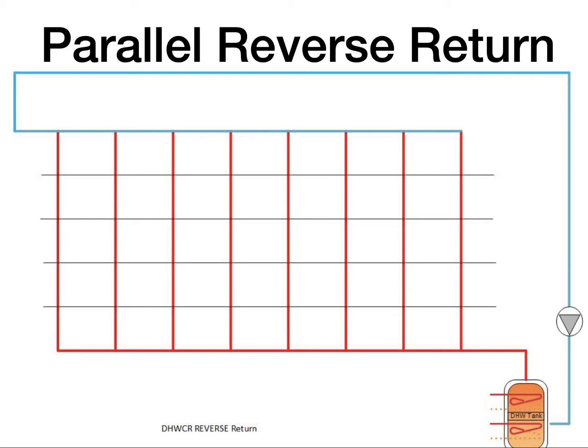However, it too is also subject to the possibility of having hydraulic erosion occurring within the piping system itself. Typically, that second to the last branch on the very top of the system is going to be ½ inch. If the circulation return pump is oversized, it is going to cause water velocities such that hydraulic erosion is a guaranteed process. By having, again, the thermal Caleffi balancing valves in there, it will basically slow the flow down to the minimum to maintain thermal structure within the actual distribution system itself and avoid the possibility of hydraulic erosion.